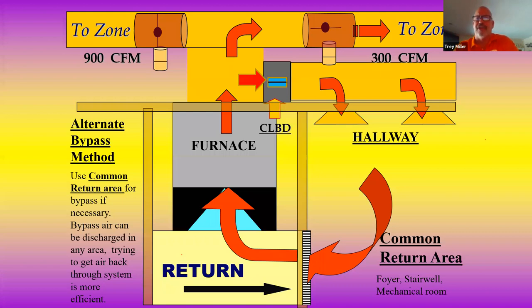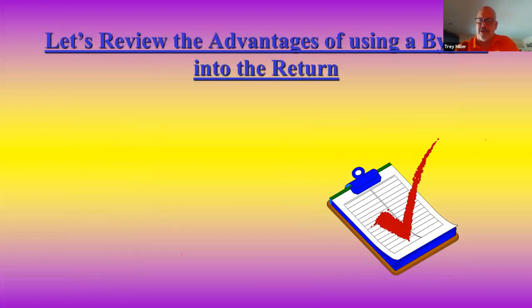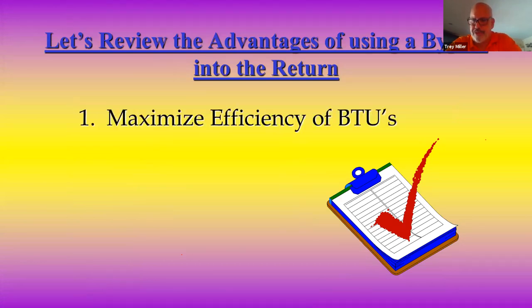Now, let's review the advantages of using a bypass in the return. One, guys, we're going to maximize the efficiency of every BTU produced. Every second that condenser runs, I'm only delivering the air to the areas of the home that need it. This is why I think zoning should be a standard in our industry. We should talk to people about this all the time. The only time you can't do zoning in retrofit is if you can't access the ductwork.